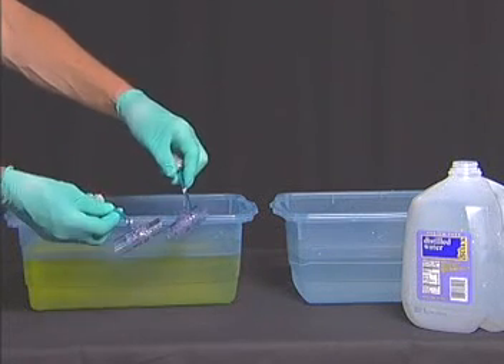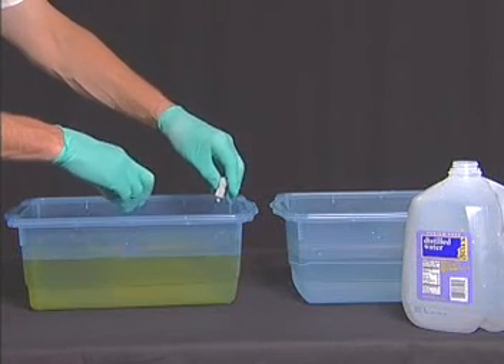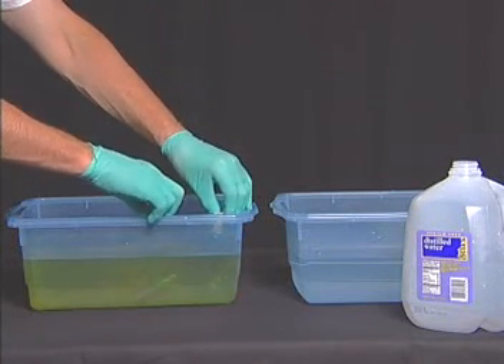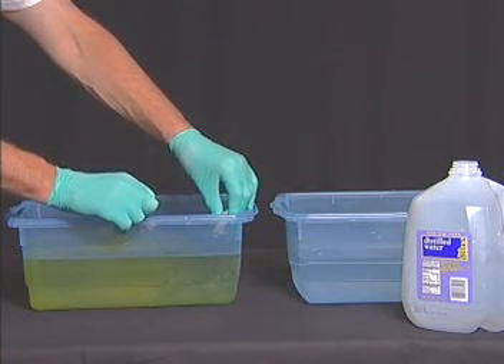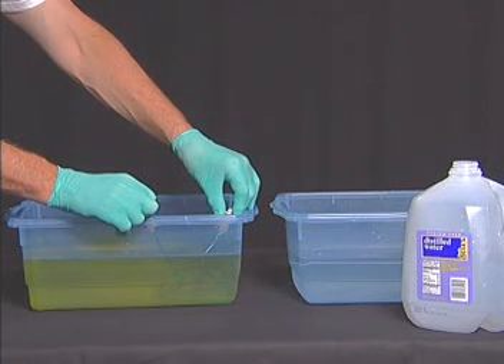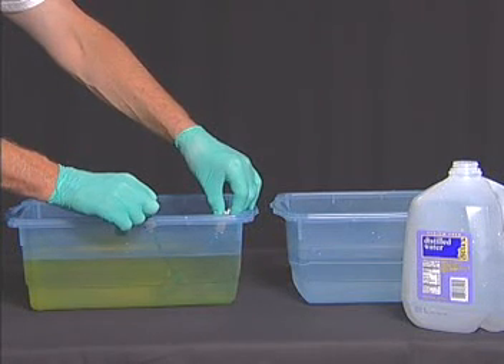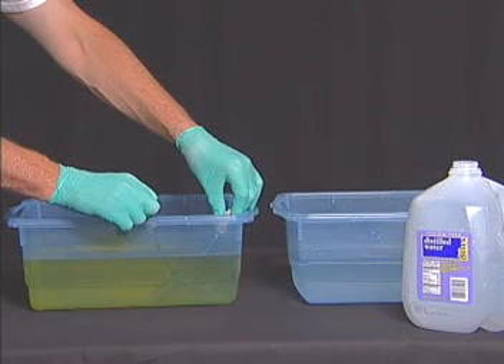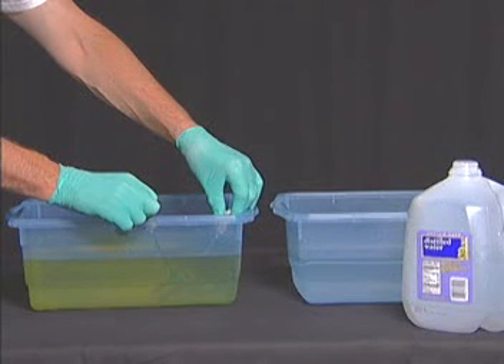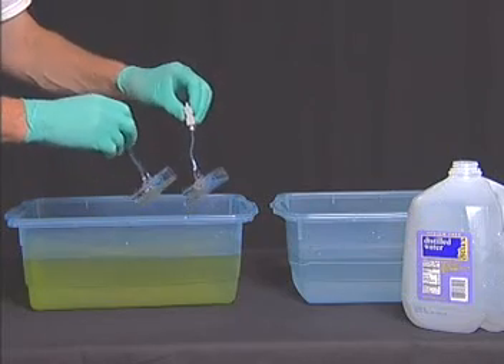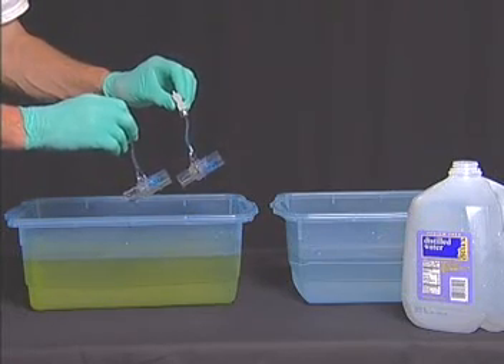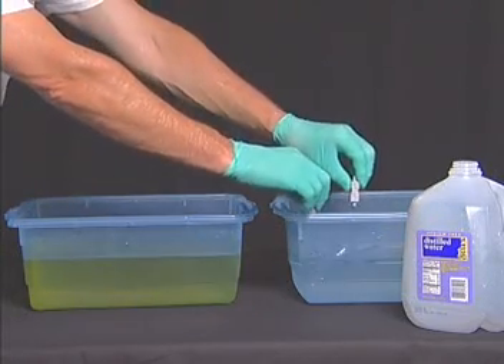If you wish to clean the flow sensors, you may do so after removing them from the flow sensor holder as described earlier. Submerge the flow sensors in tubes in activated Cidex solution. Please note that the plastic flow sensors cannot be autoclaved, and for all types of flow sensors, you must make sure to keep the connector dry. Keep the sensor in the solution for the sterilization period.